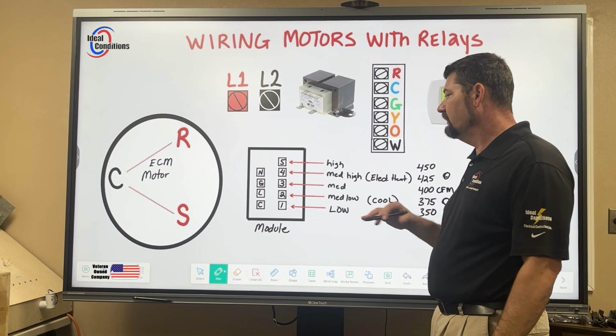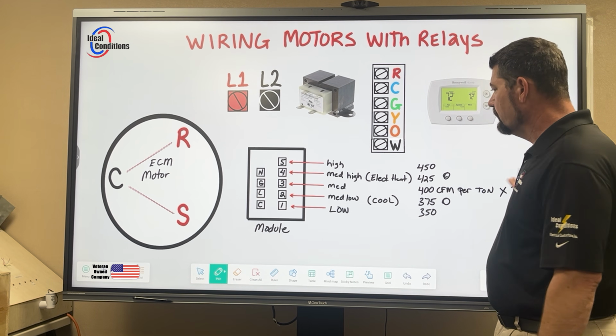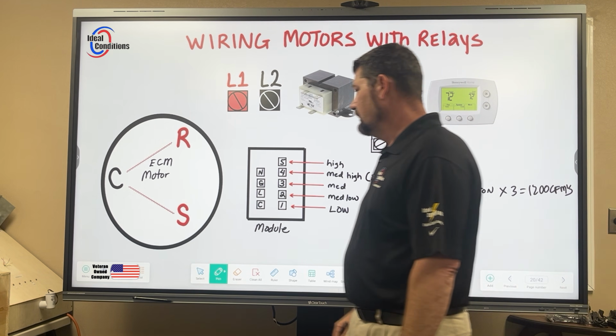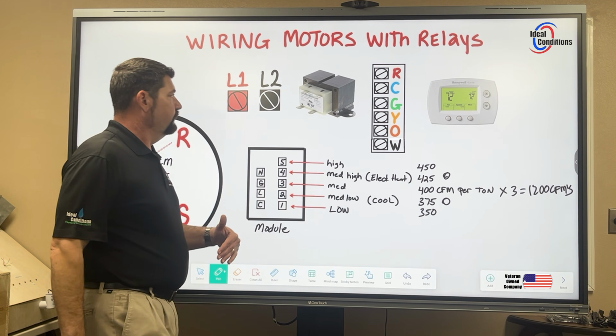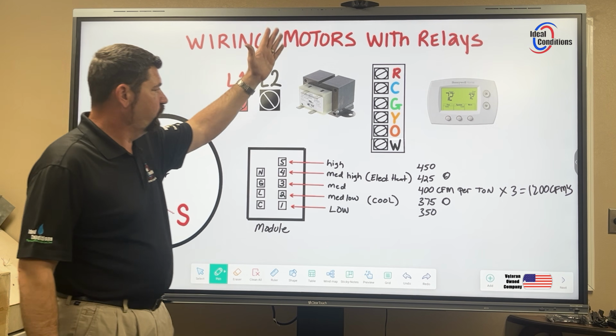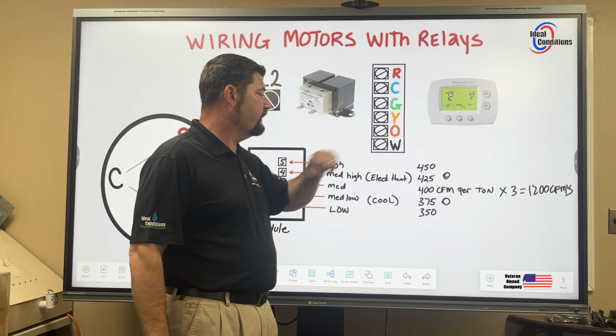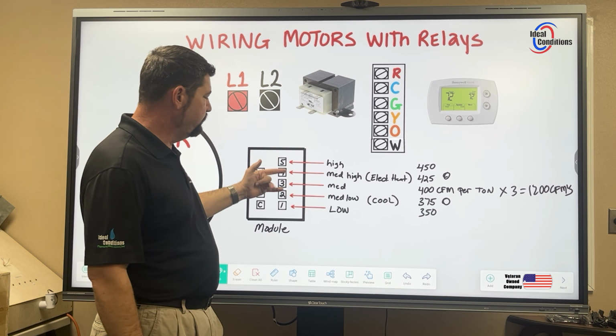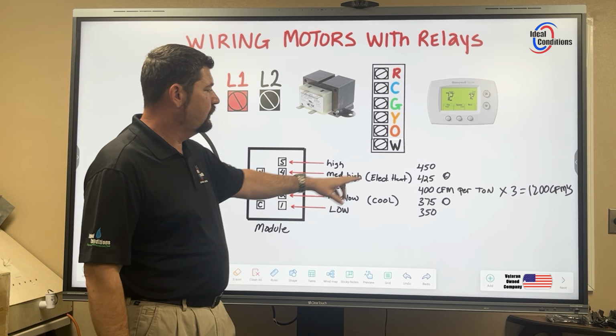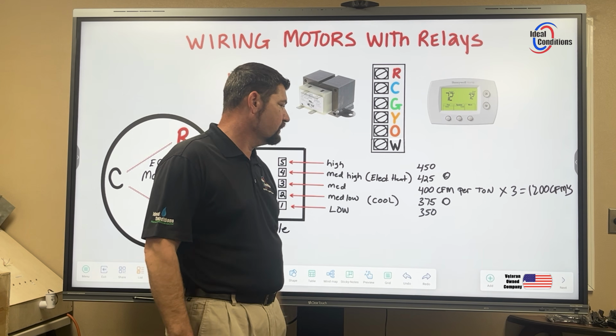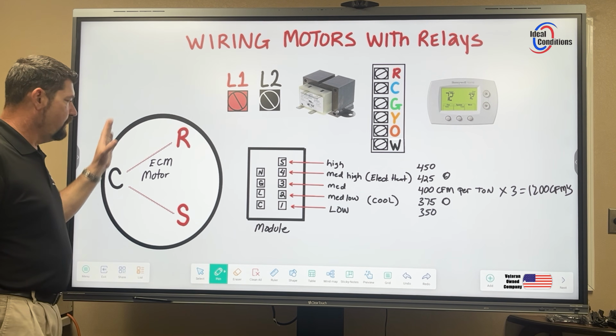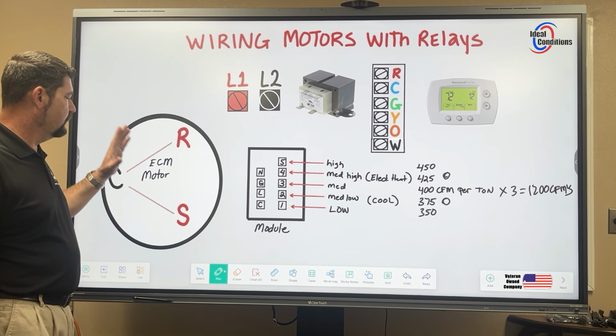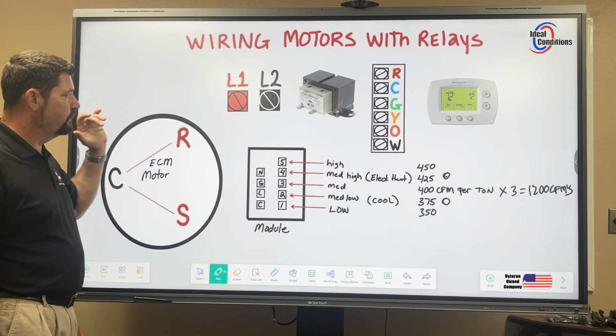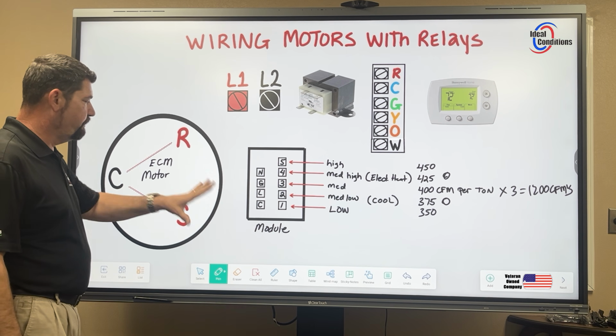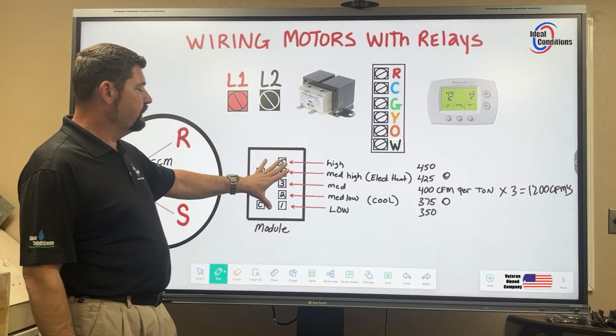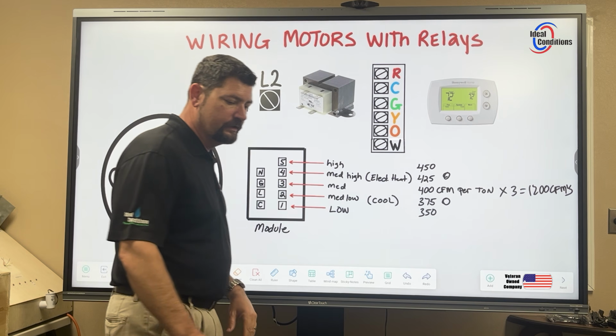Getting right into wiring this up, I'm going to leave this here for a second before I erase it. Just like in the other videos, we had L1, L2, transformer, the low voltage terminal block. You can see here I've added the Y. That's because I have 2 speeds that I can actually now wire to. So I'm putting my W terminal there, obviously, for the thermostat. This is the same motor diagram we used before. You're putting 2 legs of power there. All this stuff, there's no capacitor here because that's going to be built inside the module that I don't have expressed here in my diagram.